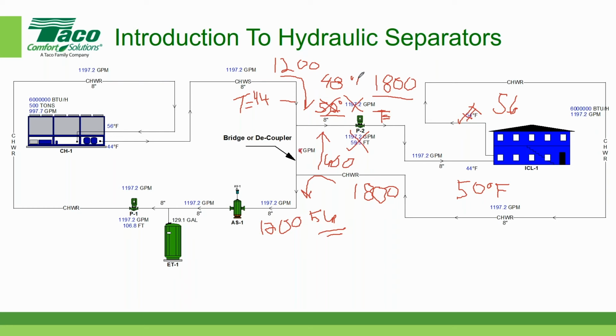So this water temperature is now going to be 48. So at 48 degrees, so this is 48. It's higher than our original temperature. And so at 48 degrees, we may, in fact, not have a low enough temperature to provide the necessary dehumidification.